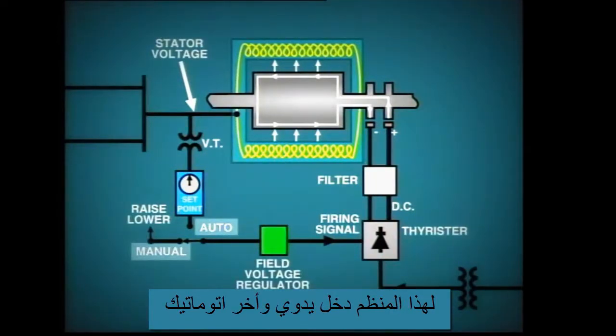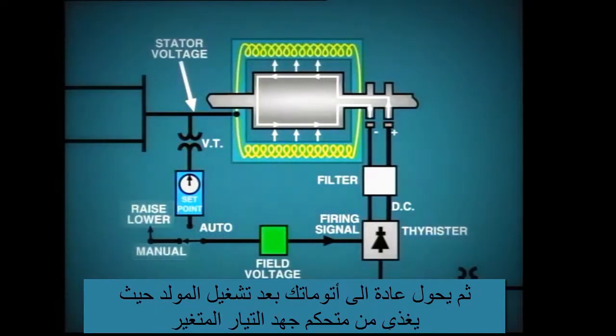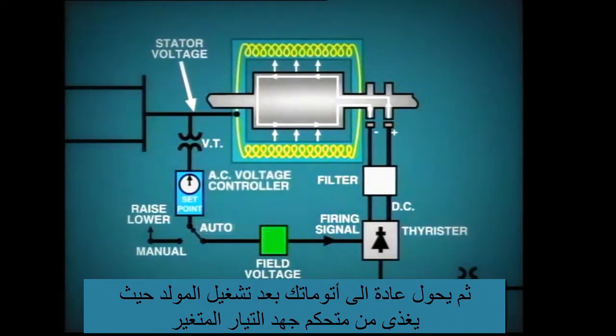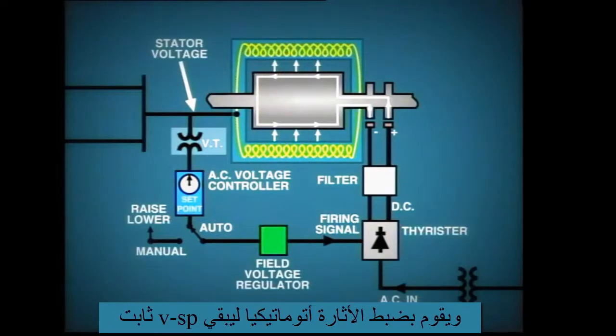The manual control disconnects the automatic function and allows the operator to directly control excitation. However, when the generator is in operation, the field voltage regulator is usually controlled from the auto position, that is, from the AC voltage controller. This controller monitors the generator bus output voltage through VTs, and automatically adjusts excitation to maintain the set point voltage.